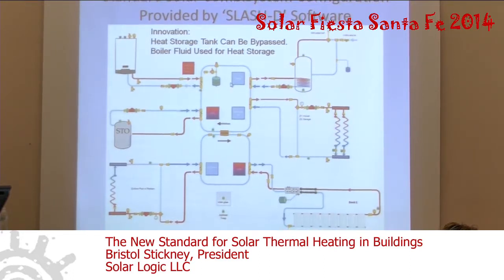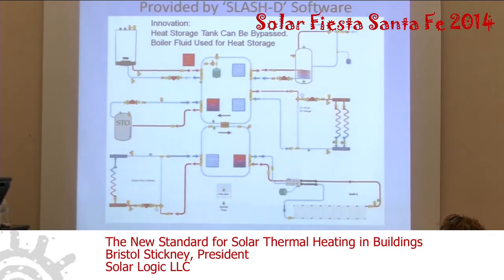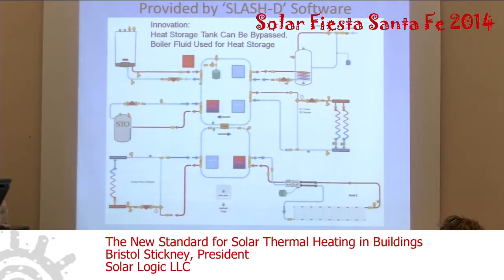And it has all the details that the block diagram did not have. It shows you where to put the pump. It shows you where to put spring check valves. It shows you where to put swing check valves. It shows you where to put the T's, the pairs of T's in relationship to one another around the loop. It shows you the order to put them in, where the boiler comes first, the DHW comes second, the floor heating comes third around the loop. It shows you everything you see here. And this is generated by a computer design program that's free that you can use over the internet.